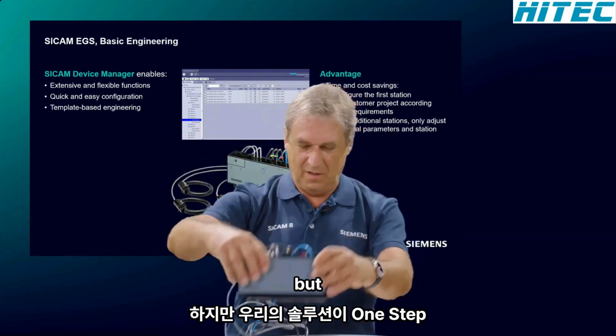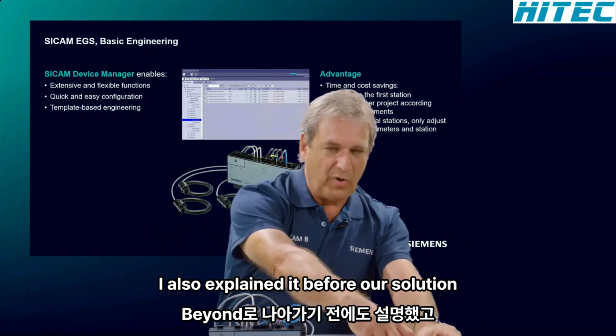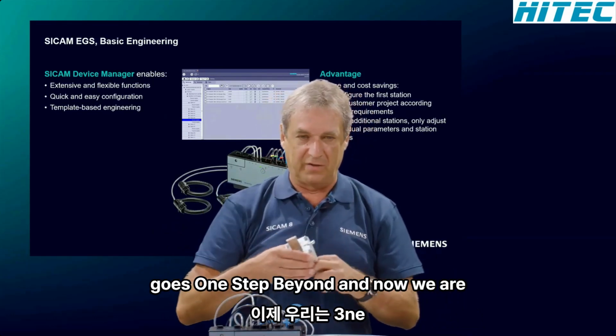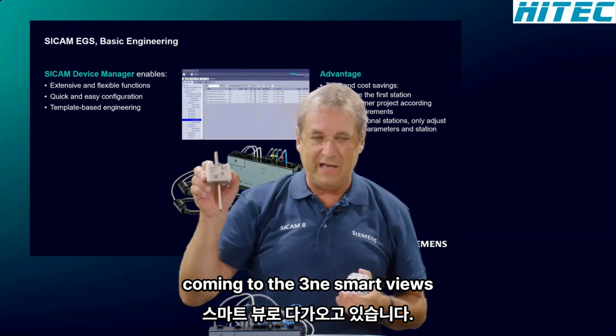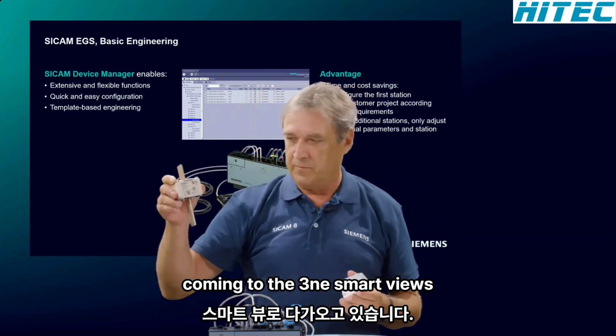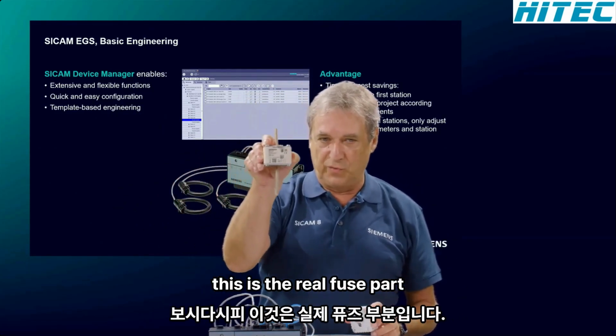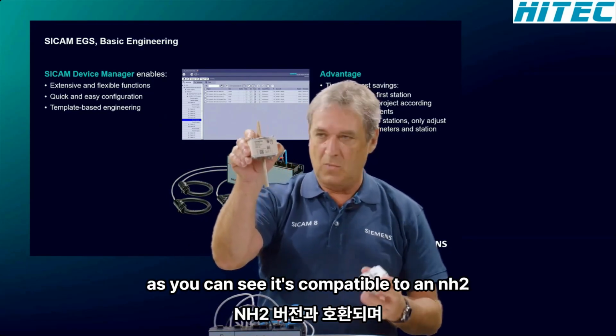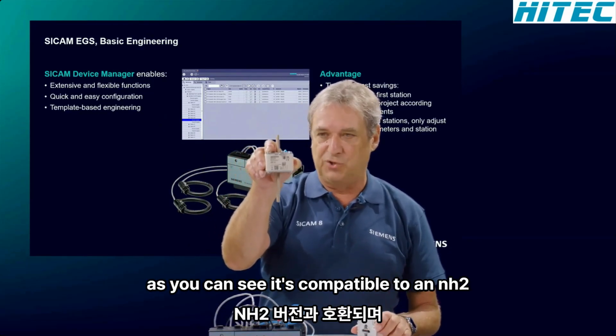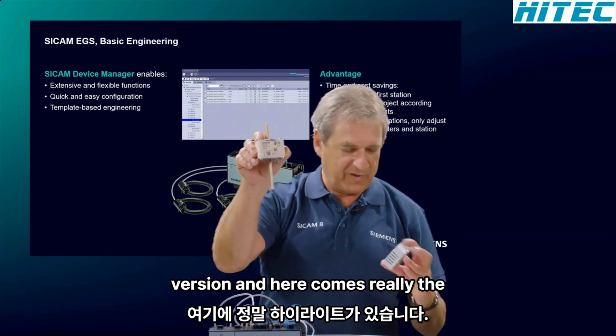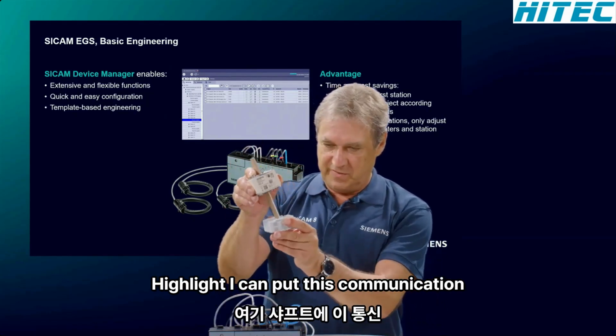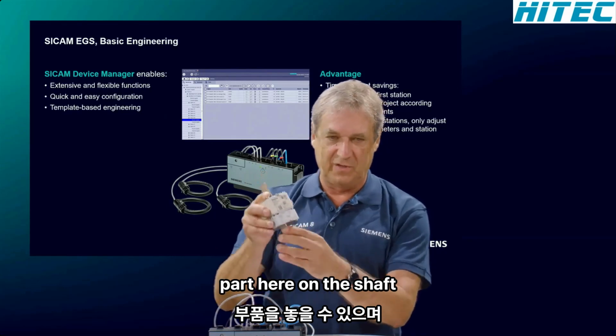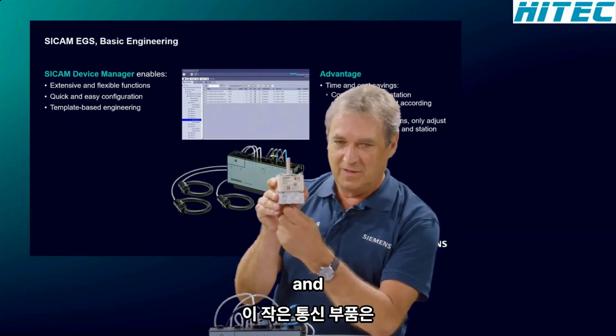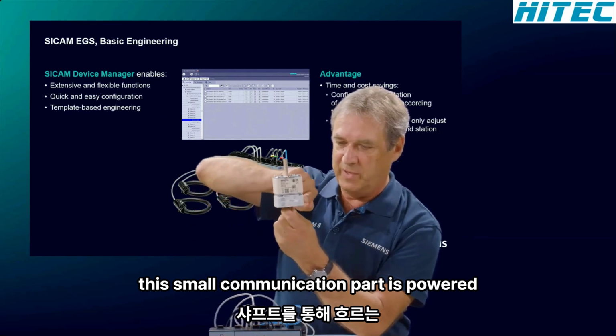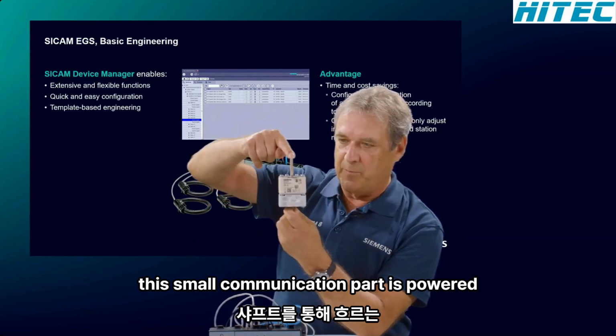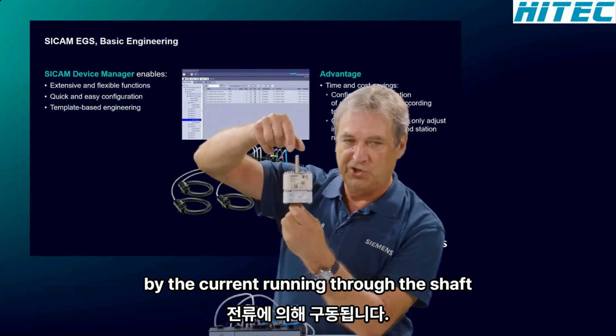But I also explained it before, our solution goes one step beyond. And now we are coming to the 3NA smart fuse. This is the real fuse part. As you can see, it's compatible to an NH2 version. And here comes really the highlight. I can put this communication part here on the shaft. And this small communication part is powered by the current running through the shaft.